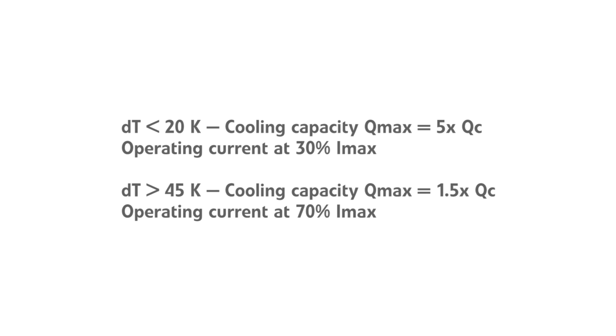As a rule of thumb, for temperature differences smaller than 20 Kelvin, the cooling capacity of the Peltier element should be around 5 times the total cooling capacity necessary. Then we operate this cooling capacity with up to 30% of Imax. For temperature differences larger than 45 Kelvin, the cooling capacity of a Peltier element should be around 1.5 times the total cooling capacity necessary. We operate then this installed cooling capacity with up to 70% of Imax.